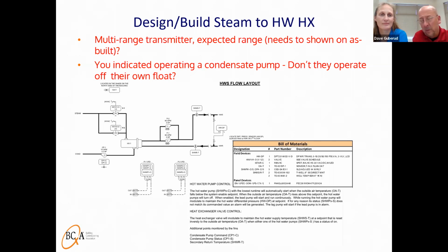And then we'll say goofy things on this. They showed a command on a condensate pump, and typically condensate pumps are float operated, and so a status is great, maybe a high level switch if it had it, but we didn't even think a command was appropriate in this instance.